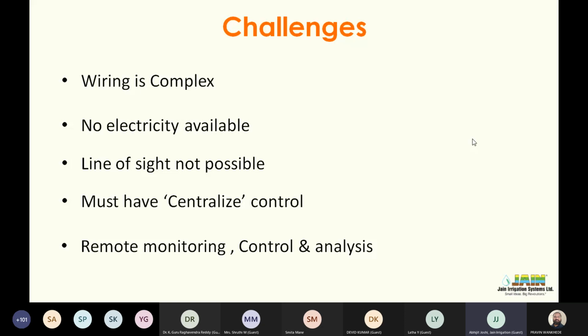You cannot say that even though the pipeline is broken down and my pressure sensor has noticed it and an alarm is generated, because my frequency of handshaking is say 5 minutes, I cannot get any data for 5 minutes. So you need to work out a scheme in which when there is an alarm, your RTU shall immediately start giving signals to the gateway or base station. So these are the challenges which we usually face in handling such agricultural IoT systems for community-based irrigation projects covering 1,000 hectares of area.